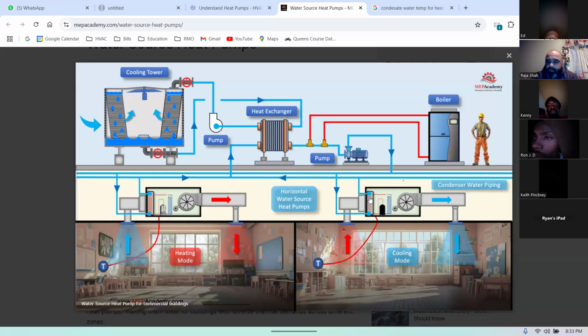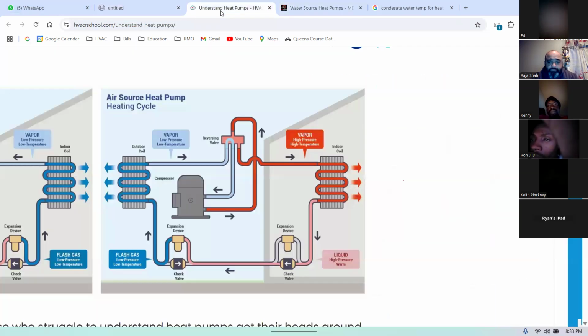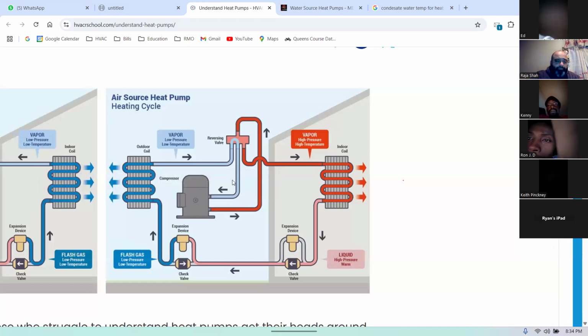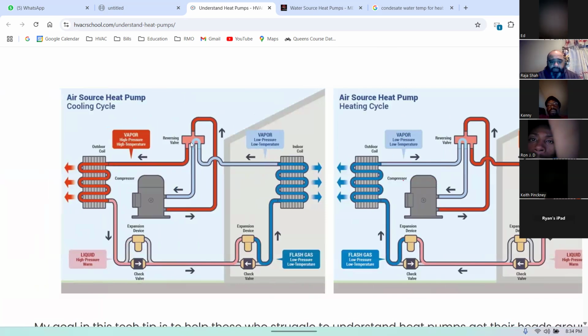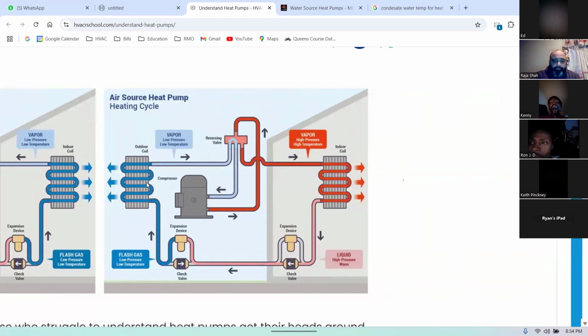The condenser is actually becoming the evaporator coil, like over here. Roles are in reverse, right? So now it's picking up heat from out here, and then through the reversing valve, it's now your discharge line. What was your discharge line over here? You see, this was your discharge line before, guys. Now it's going in reverse.